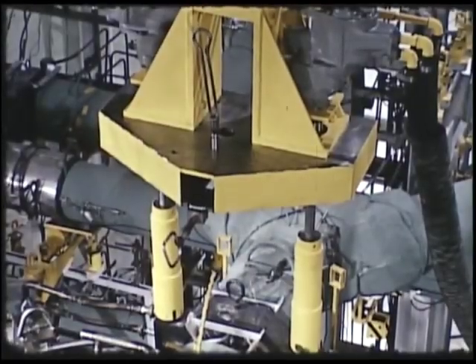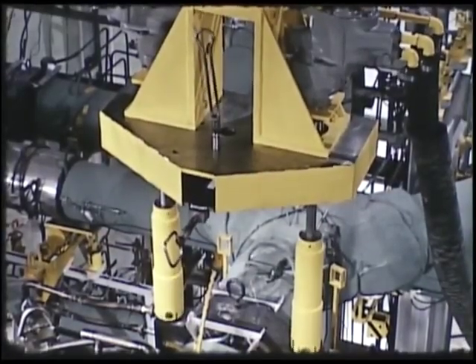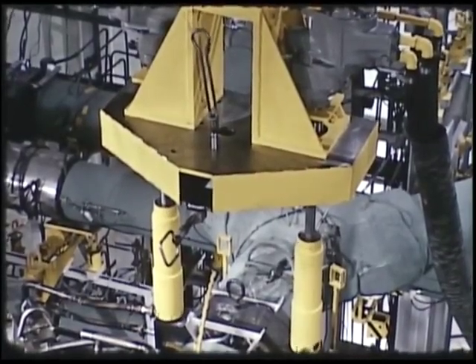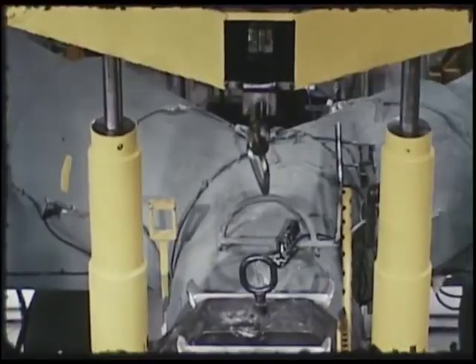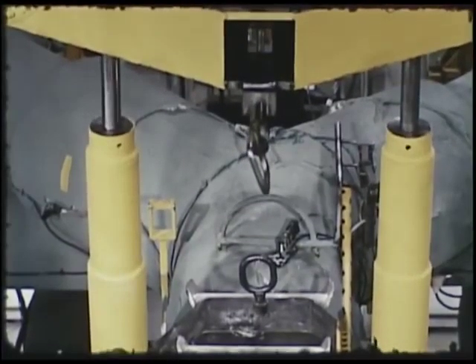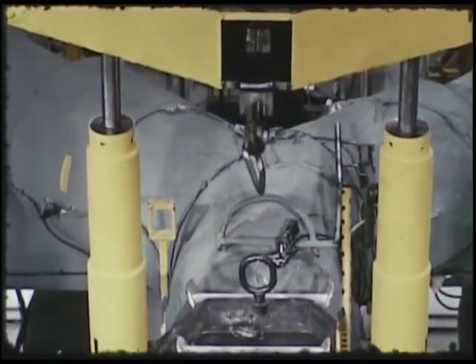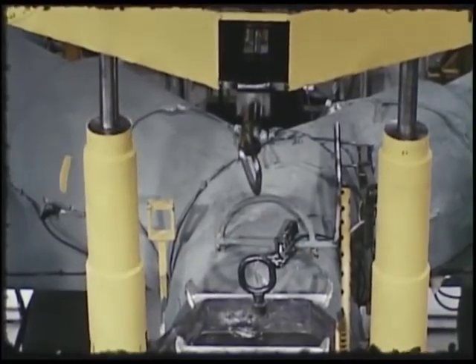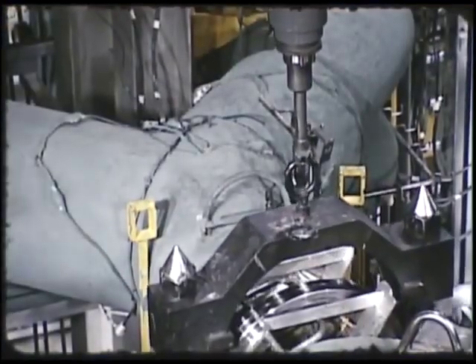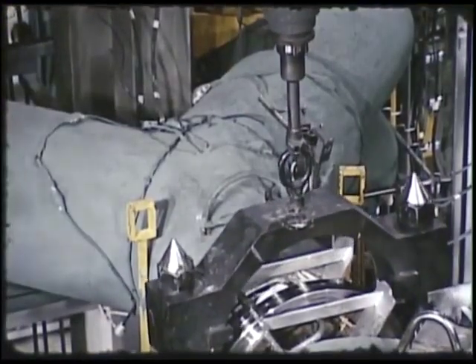The same tool, after conversion to a bolt runner, unscrews the bolts until the clamp halves separate far enough to slip over the flanges. One of the air motors simultaneously turns both 2 5/8-inch socket extensions through a geared drive. This unscrews both bolts the same number of turns. The loosened flange clamps are moved aside.